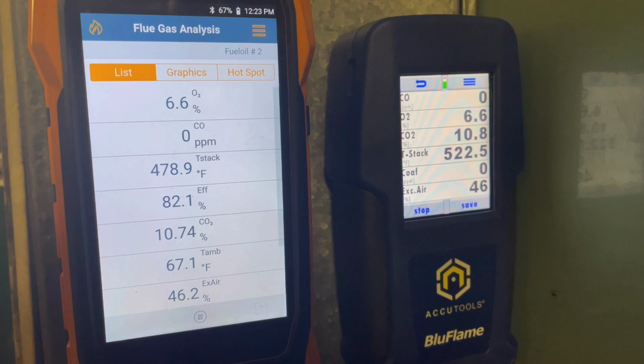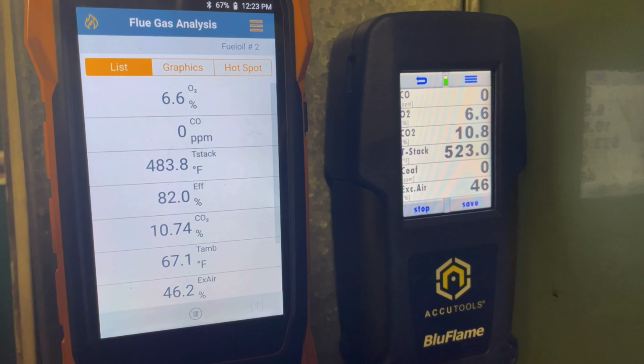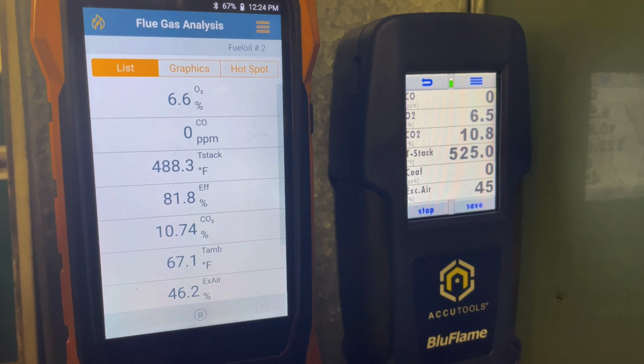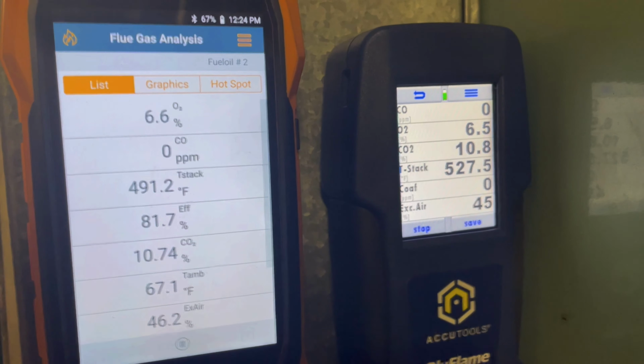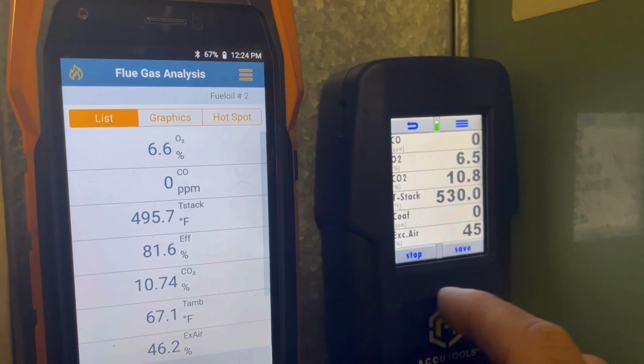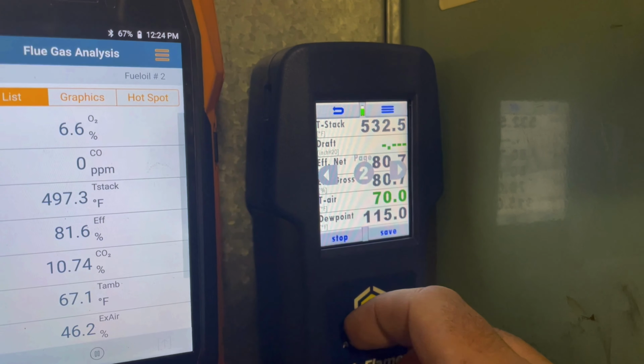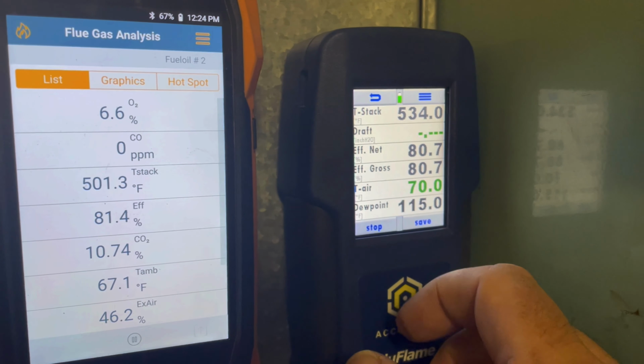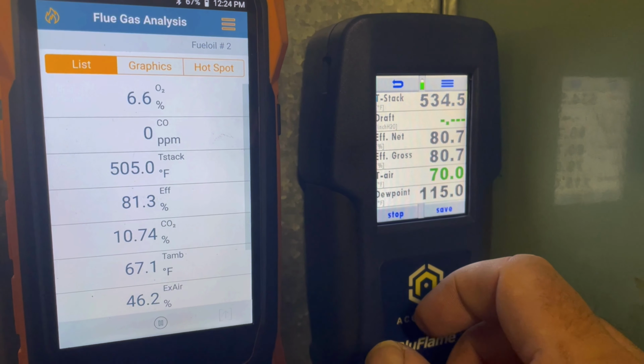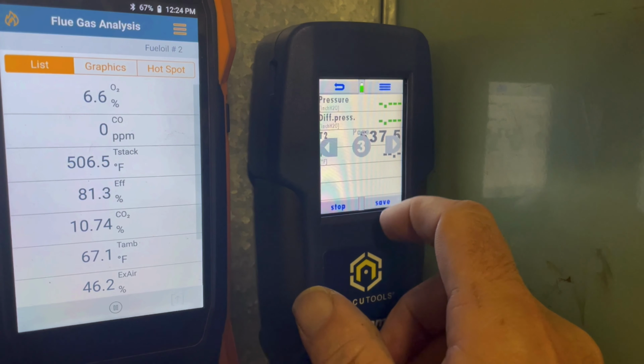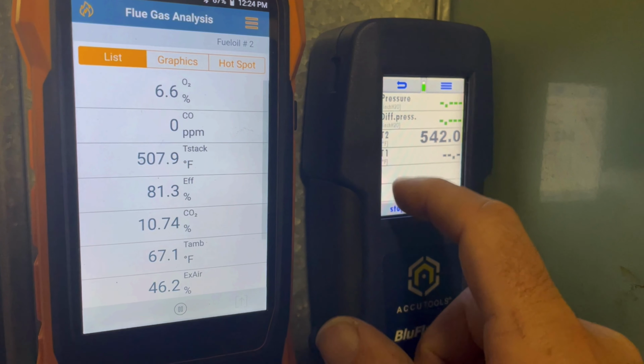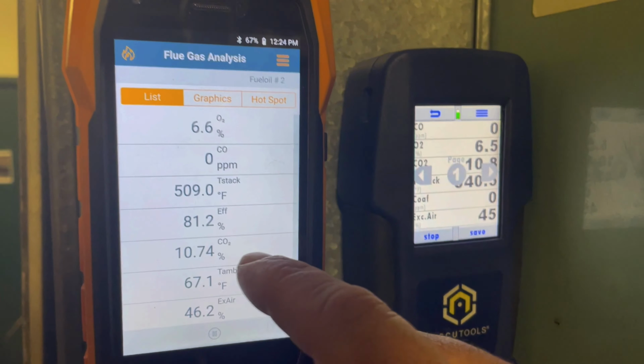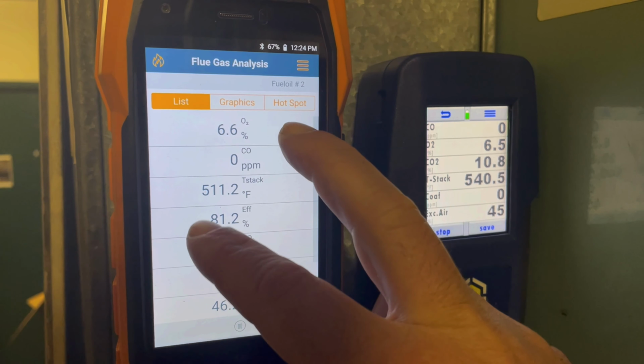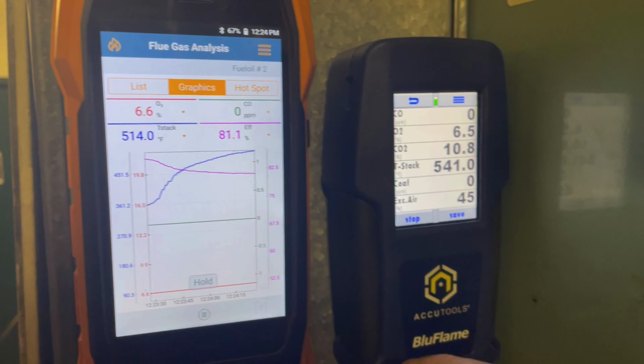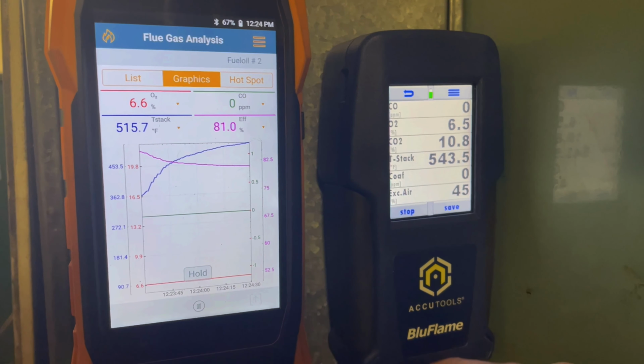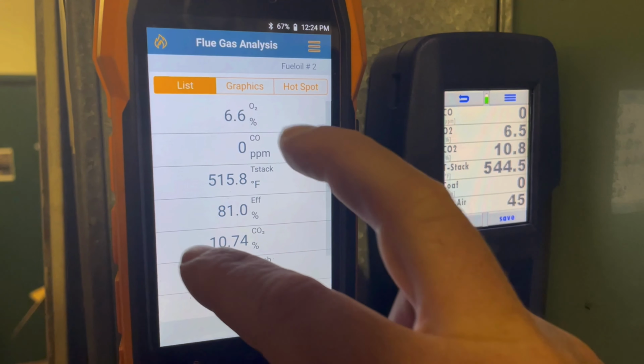So you can see on the Testo we're about 10.74%, and the BluFlame is at 10.8. Looks like all the information is pretty similar. There's a slight difference in stack temperature. Earlier, it was relatively close. Maybe my Testo got a little colder. Testo does have a graph on the machine, which is very helpful.